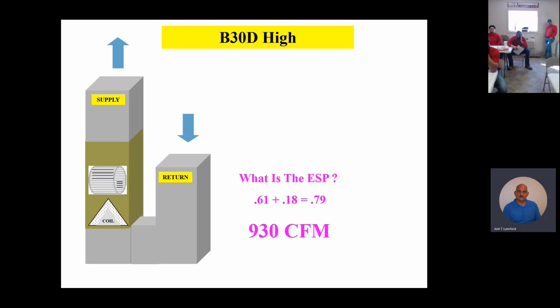For the most part, most manufacturers like to see their equipment running at about a 0.5 or a 0.55 total. And this is another reason, by the way, I like to take my static pressure reading separately. Where am I having the most resistance on this unit, on the supply or the return side? So again, that's why I like taking them separate. So I have 0.61 on the supply, 0.18 on the return.